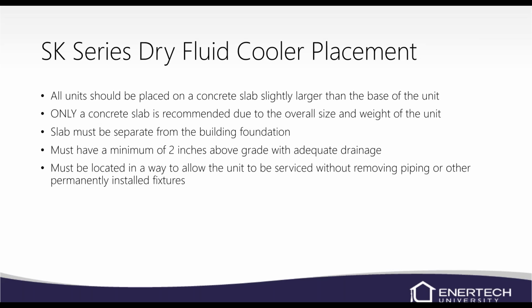You must have a minimum of 2 inches above grade with adequate draining on that pad. You don't really want water to stand on that pad. It has a tendency to freeze and then break the concrete. So you may want to make sure it's draining properly.